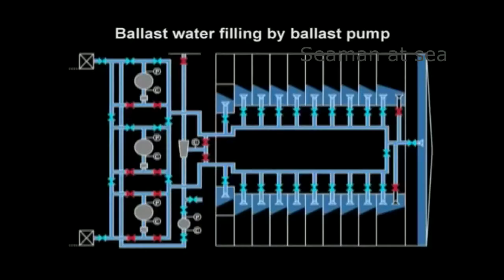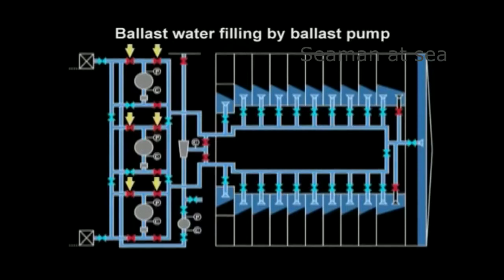After ballast filling by gravity is over, let's proceed to filling by means of ballast pump. Before starting the ballast pump, completely close the discharge valve. Centrifugal pumps are commonly used as ballast pumps. Start the pump with its discharge valve fully closed to avoid an overload at the start of the pump and to minimize surge pressure.